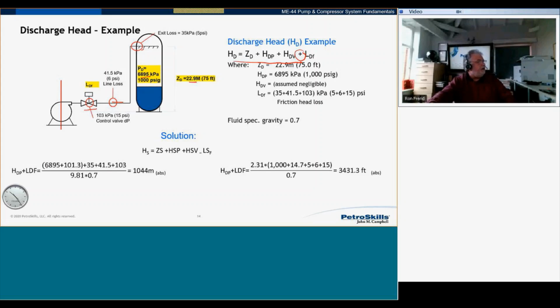If I take my 6895, which is the pressure in the vessel, make it atmospheric, 35 kPa for the exit losses into the vessel, 41.5, which are my line losses, and 103 because this is what's going through the control valve. Divide by 9.81 by 0.7, because all this is, guys, is pressure equals rho g h. Simple.